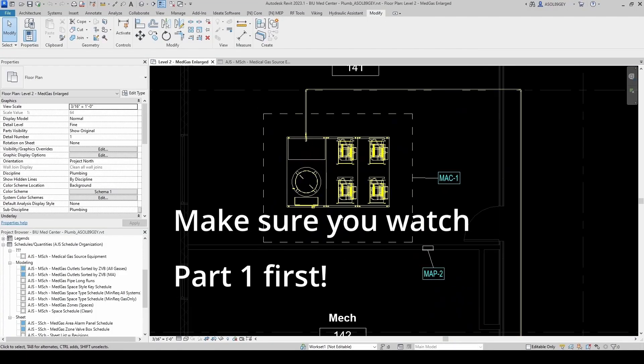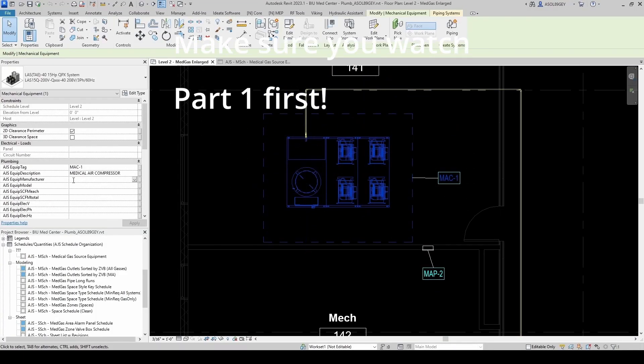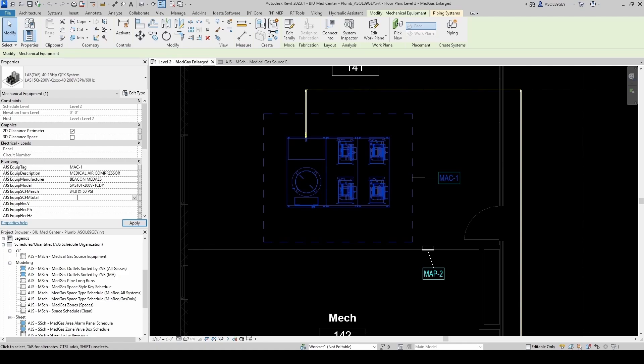And now we can just fill up our information. So the Equipment Manufacturer is Beacon Medaes. Model number is SAS 10T 200V TCDY. Standard CFM each, each one's doing 34.8 at a pressure of 50 psi. The total is two of them at the same time, even though it's a triplex. The total compressed air standard CFM is based on two out of three compressors running. So it's 69.6 and this is at the same pressure because they're in parallel, 50 psi.